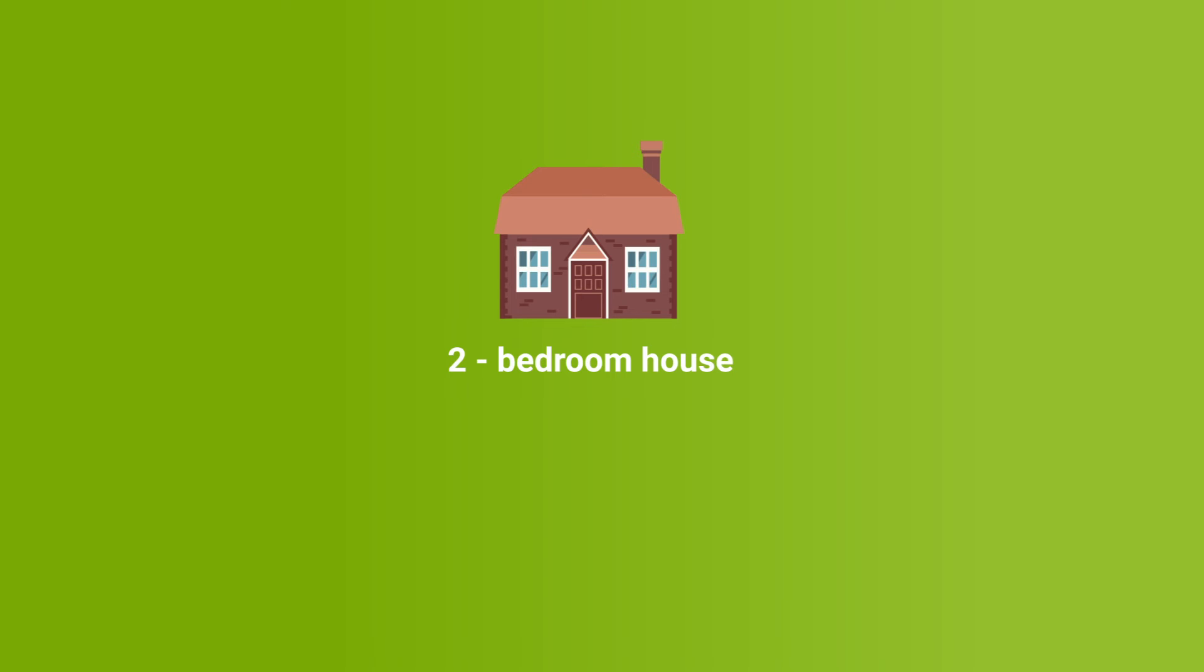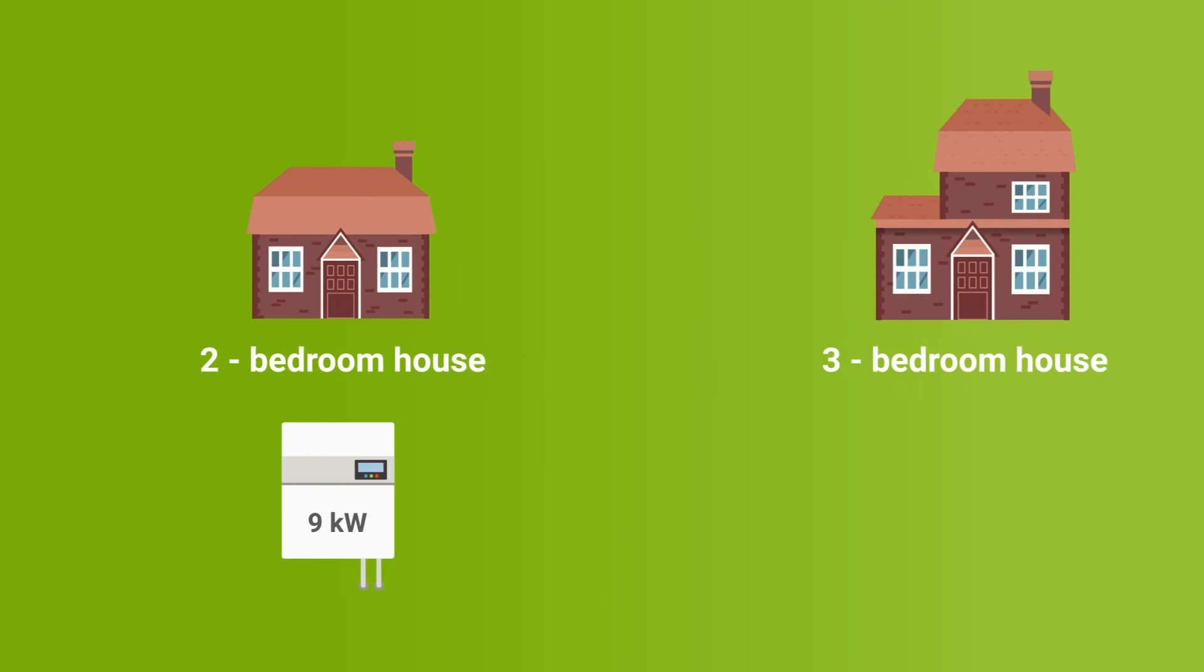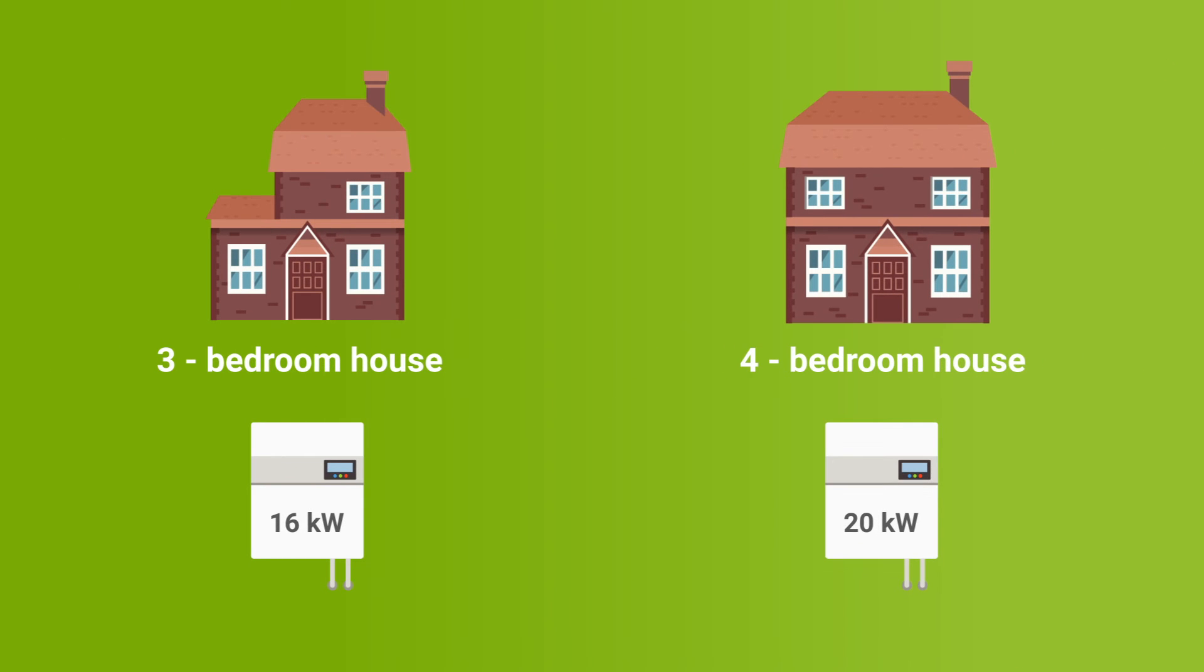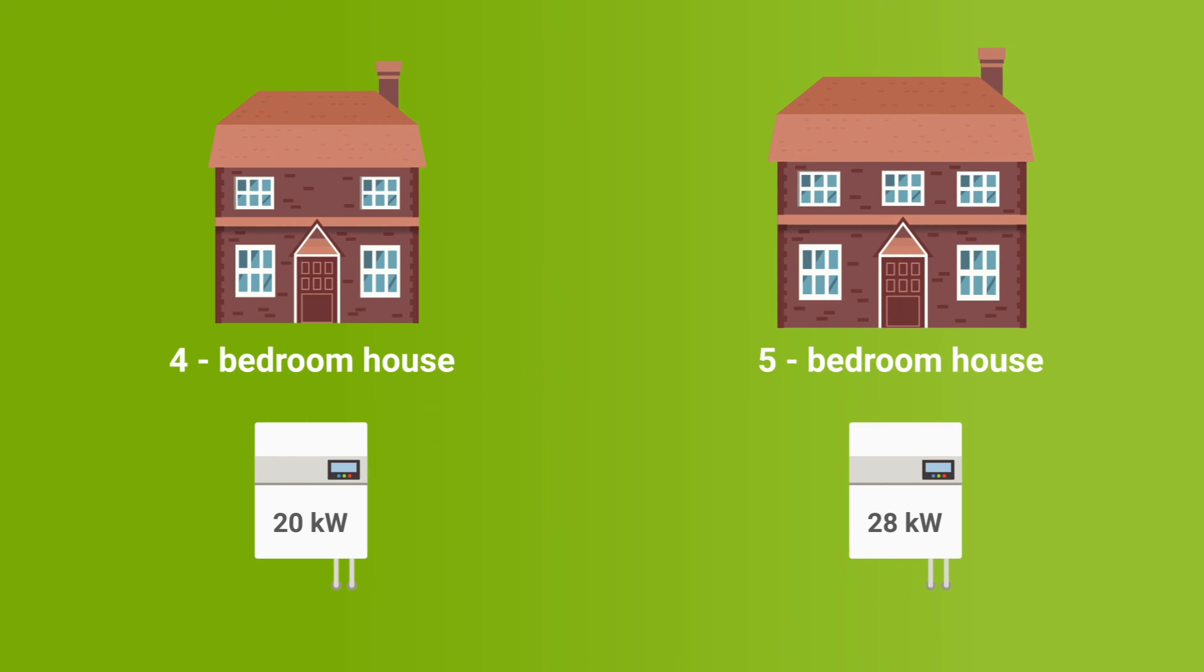A two-bedroom property will generally need a boiler with an output size of 9 kilowatts or higher. This goes up to 16 kilowatts or more for a three-bedroom property and 20 kilowatts or more for a building with four bedrooms, while a large five-bedroom home will require a boiler with an output of around 28 kilowatts plus.